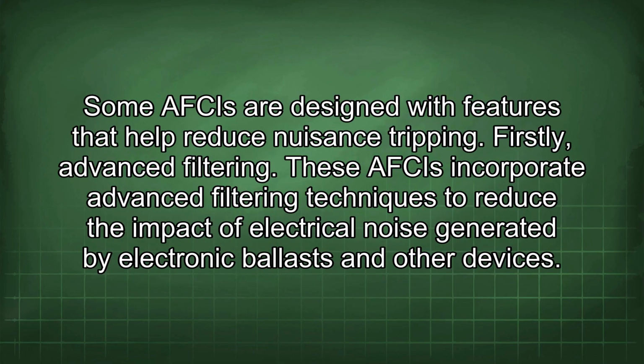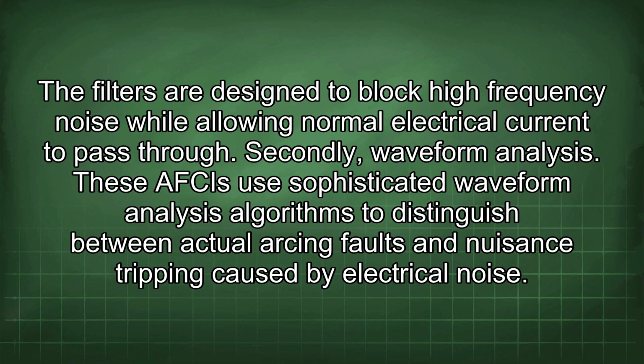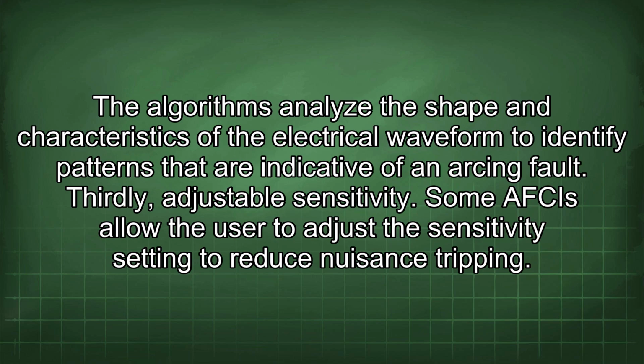Some AFCIs are designed with features that help reduce nuisance tripping. Firstly, advanced filtering. These AFCIs incorporate advanced filtering techniques to reduce the impact of electrical noise generated by electronic ballasts and other devices. The filters are designed to block high-frequency noise while allowing normal electrical current to pass through. Secondly, waveform analysis. These AFCIs use sophisticated waveform analysis algorithms to distinguish between actual arcing faults and nuisance tripping caused by electrical noise.